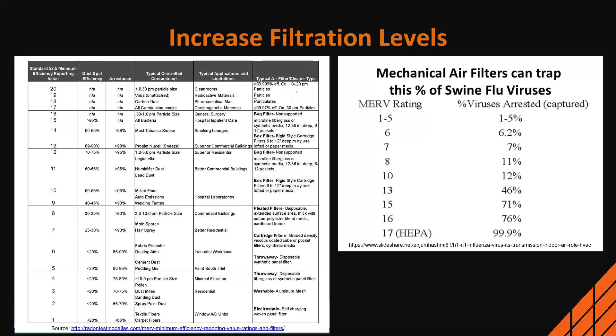Hospitals, for example, don't use it throughout the hospital. They use it in their ICU and their surgery spaces, some lab spaces, things like that. But throughout the hospital, they're using like MERV 15, things like that. So on the HEPA, the cost, the size, the static drop really kind of prohibits it from being everywhere. We may have spot locations that we might look at using it, but everywhere it's kind of a limited item. So if we take that MERV 13 and we put it in our sample system here, we're still going to run our 30% outdoor air because we're going to add our solutions together. So on that particular day, we run 30%. And now I've gone from that 11% capture of the MERV 8 to this 46 of the MERV 13.